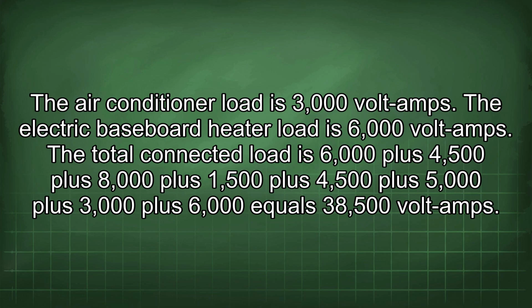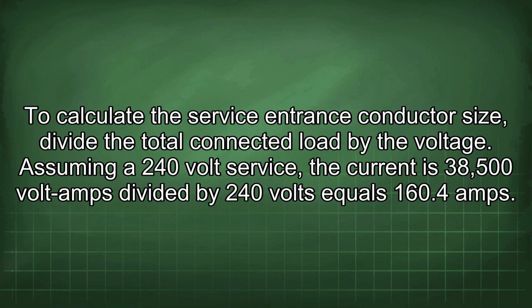The total connected load is 6000 plus 4500 plus 8000 plus 1500 plus 4500 plus 5000 plus 3000 plus 6000 equals 38,500 volt amps. To calculate the service entrance conductor size, divide the total connected load by the voltage. Assuming a 240 volt service, the current is 38,500 volt amps divided by 240 volts equals 160.4 amps.